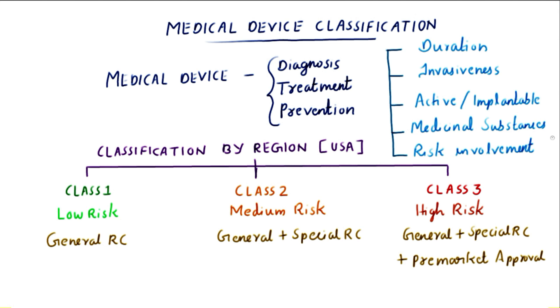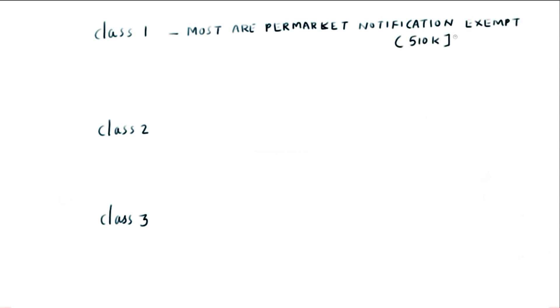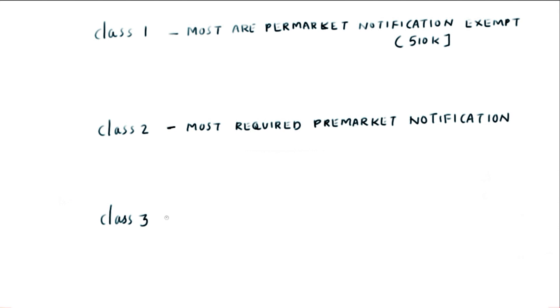Most Class 1 devices are exempt from pre-market notification. Pre-market notification, or 510(k) clearance, is a pre-market submission made to FDA to demonstrate that the device is safe and effective, or equivalent or better than an existing legally marketed device. Most Class 2 devices require pre-market notification, and most Class 3 devices require pre-market approval.